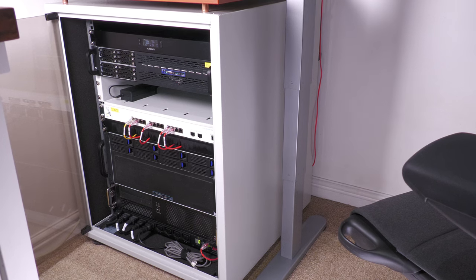But in winter, for example, if the room started getting a bit colder, it's currently about 23 degrees inside, and in winter it's usually about 19 degrees inside, at that point the rack would be running a lot cooler and we'd start having the fan turning off. So it may be a case that throughout the year I might need to adjust the set temperature just to keep it at that speed where, on average, it's generally sitting around fan speed 1 and it can increase if it needs to. So yeah, one little complaint there, but other than that, it works really, really well.